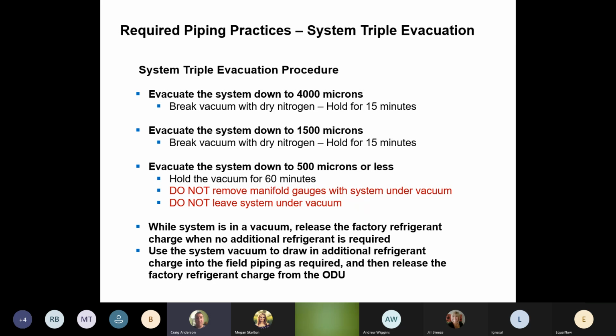Once we know it's held, let's go to the next step. If it needs to add gas, let's add the gas while it's under a vacuum. Put the new gas in it and then crack the lines outside. Add the gas before you crack the outdoor unit, because some of these systems have low pressure switches on them. If you've got an 80-foot line set, or 50 feet or whatever, you're probably going to add a pound or two of gas to the unit depending on your system.